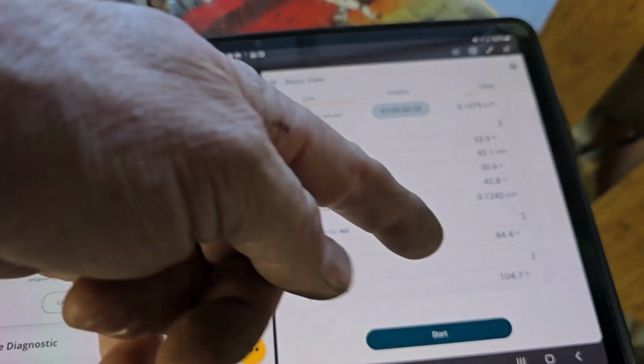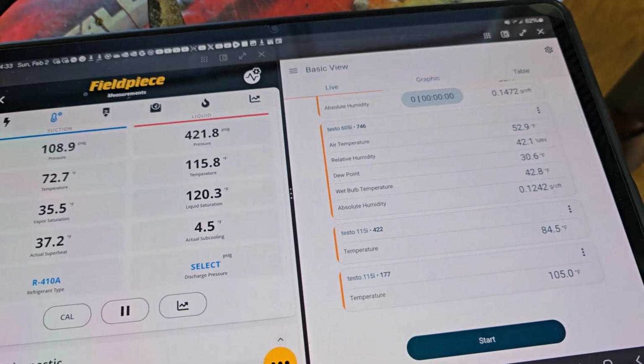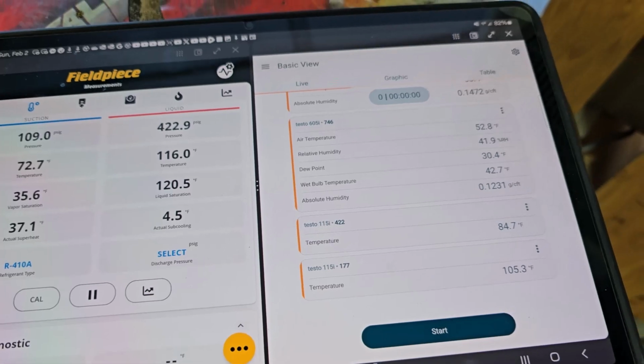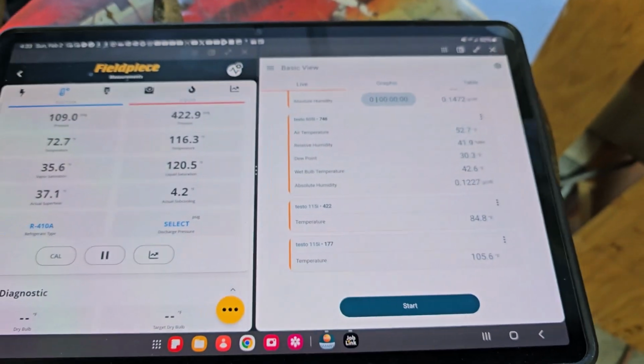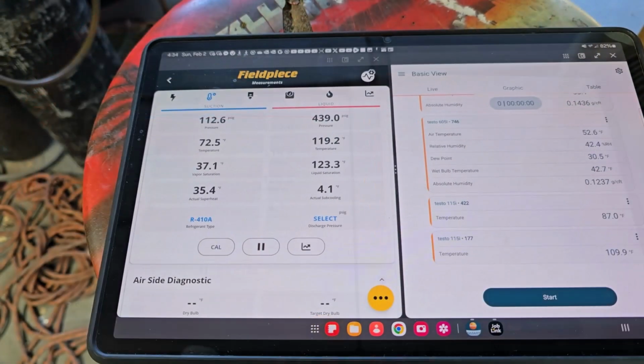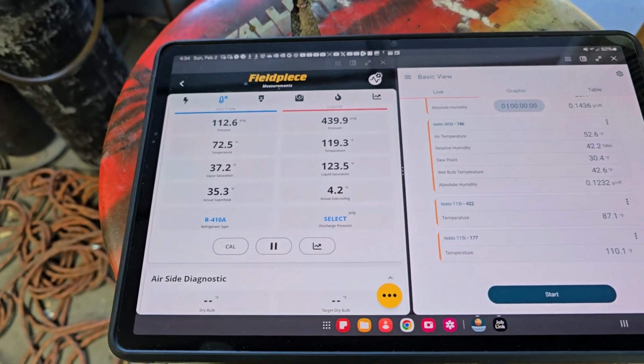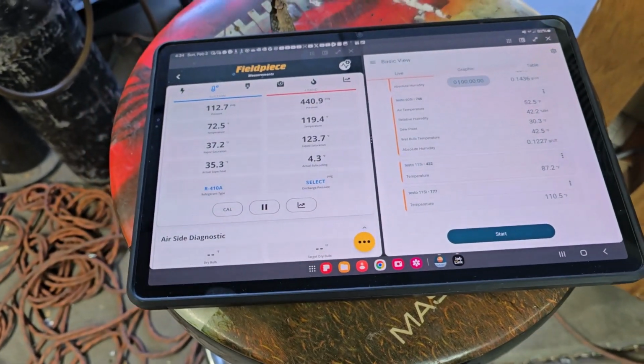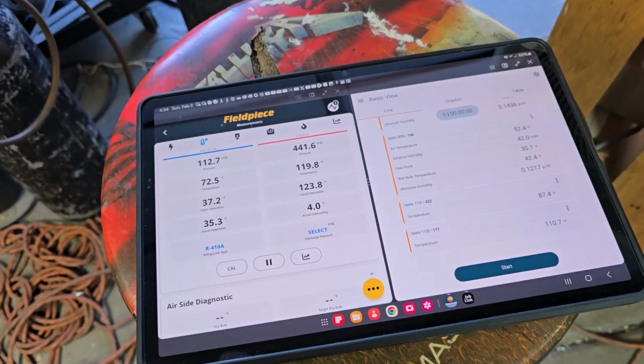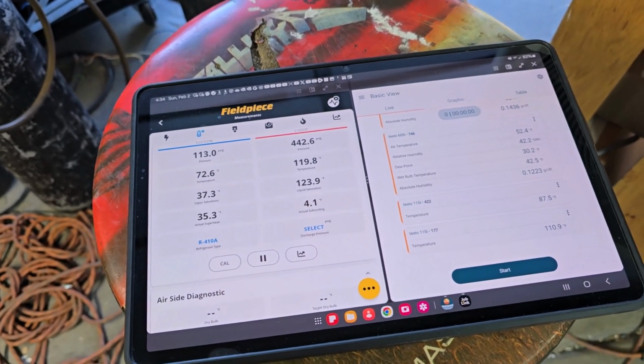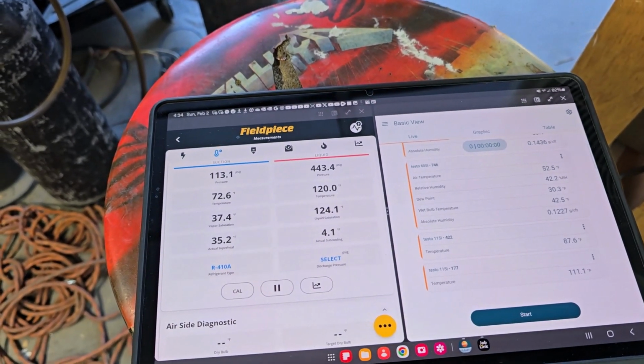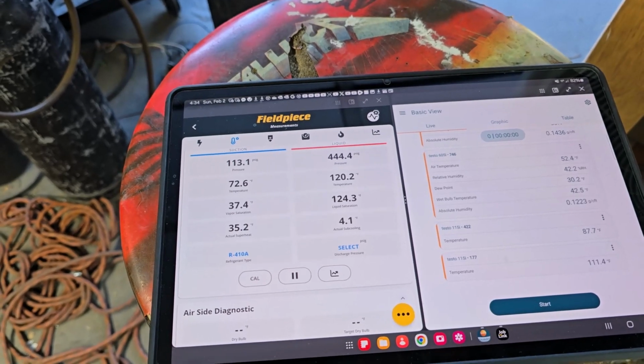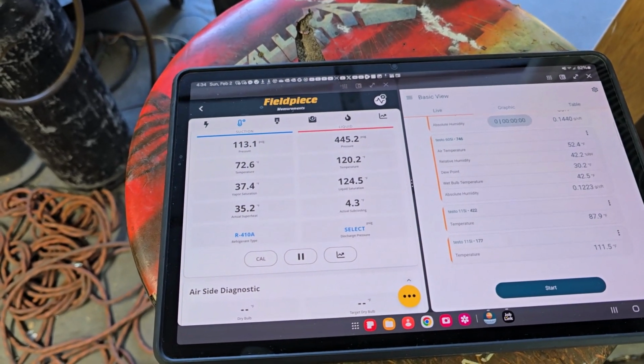But what I like to do is I like to have it staged, and I'll have to recalibrate this one since it's a different unit, but I like to do it so it only discharges really hot water. So it's creeping up there. Obviously, when you use a heat pump to heat water, you kind of run it a little high when the tank water temperature gets high. You know, you're pushing the compressor a little bit, but I mean, it's just the nature of it, you know.